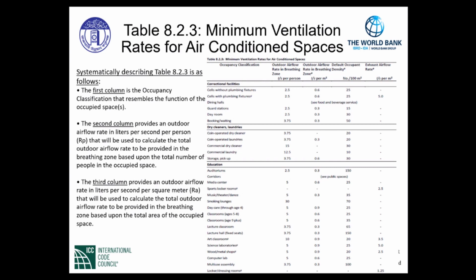In an education occupancy classification for auditoriums, the minimum outdoor airflow rate in the breathing zone that we'll have to calculate is 2.5 liters per second per person. This is where we pick this variable, and we will integrate this variable into an equation and ultimately calculate the total outside air requirement for mechanical ventilation. This is just one part that we have to integrate into an equation that I will show you coming up in a slide later on.